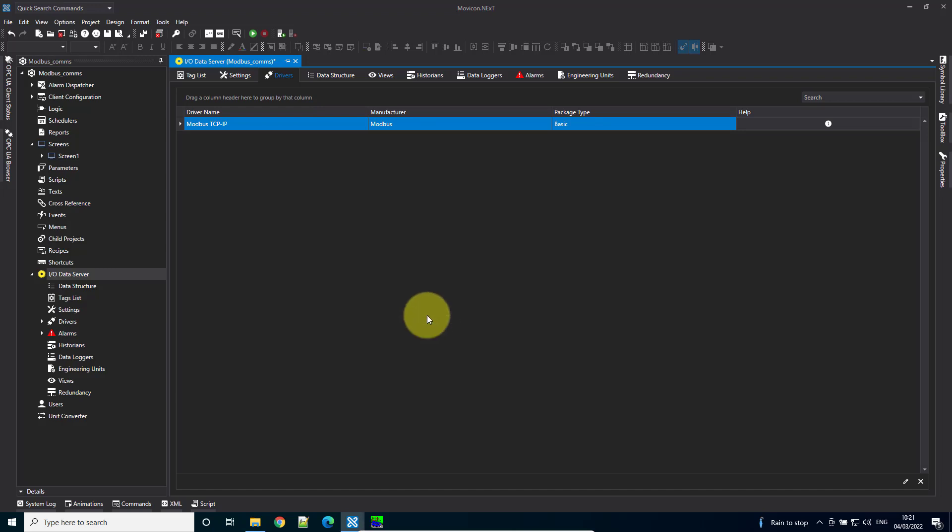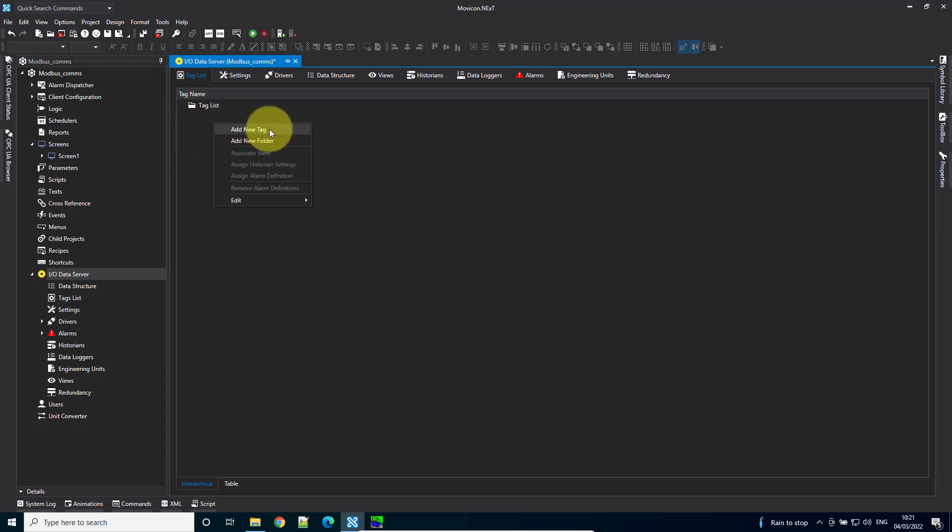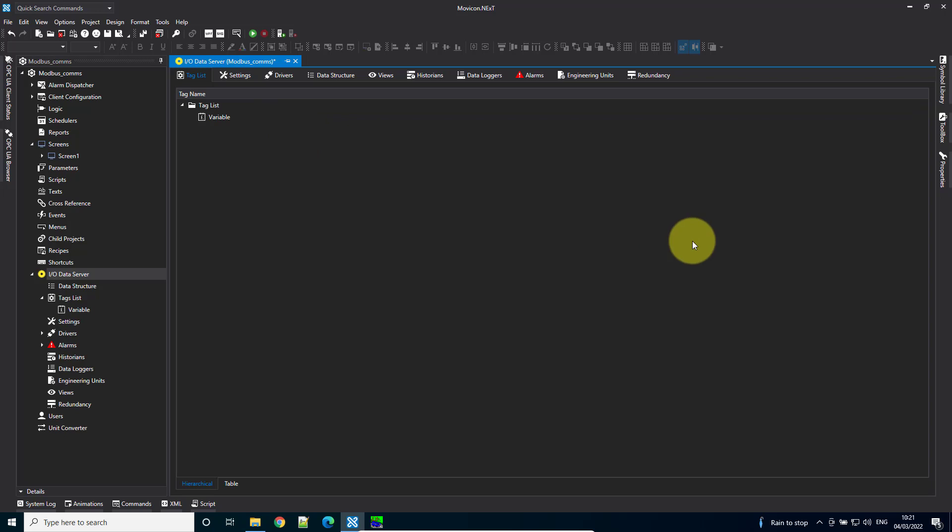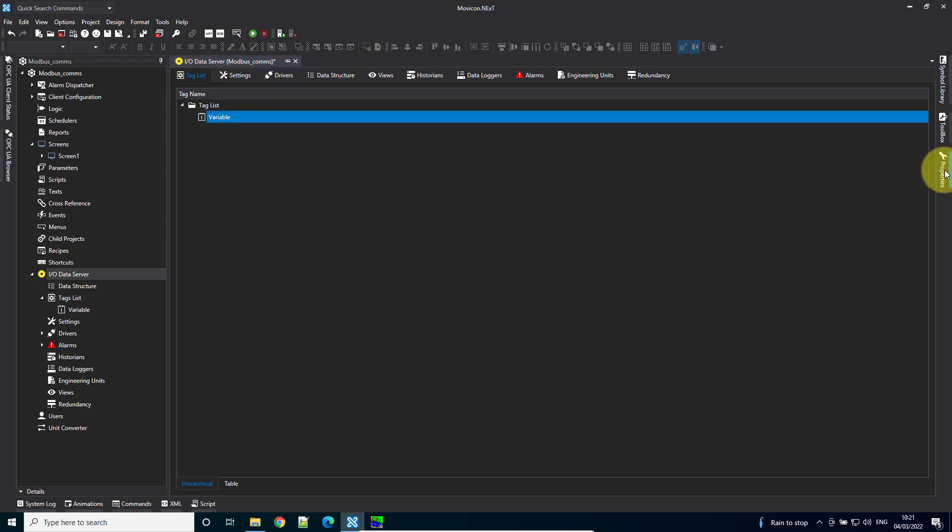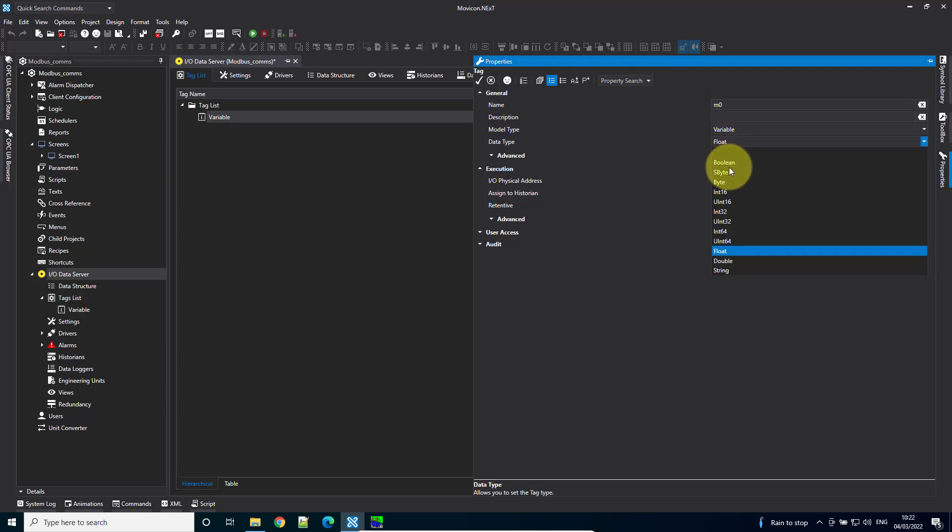Now let's create a couple of tags. Go to the tag list, or address space on your machine—it's the same place. Right-click and add a new tag. In the properties, I'll call this M0 because we're looking at holding register memory location 0. Set it as an integer.